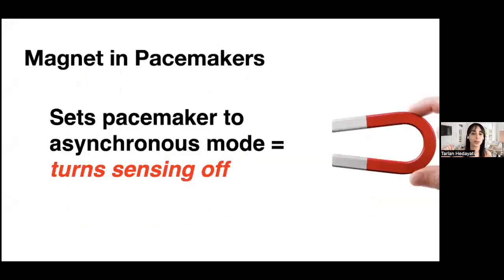So what does a magnet do with a pacemaker? When you put the magnet on the pacemaker, it sets the pacer function to asynchronous mode, which means it turns the sensing function off. When you turn the sensing function off, you're telling it to stop running surveillance. If it's no longer running surveillance, it doesn't have the ability to get triggered or inhibited, so essentially it's just going to pace. By putting a magnet on a pacemaker, you tell the pacer, just start pacing, and that's what happens when you have failure to pace.